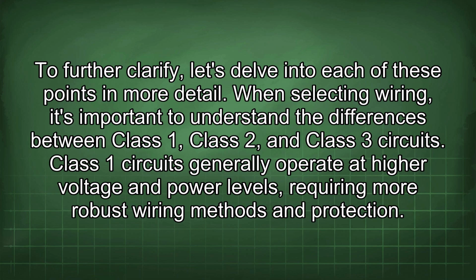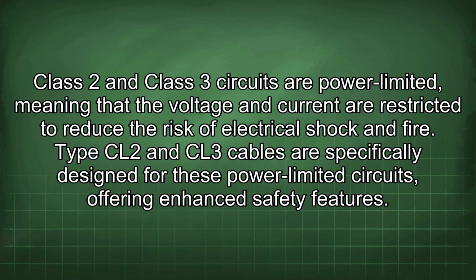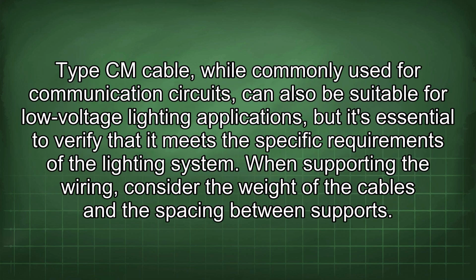When selecting wiring, it's important to understand the differences between Class 1, Class 2, and Class 3 circuits. Class 1 circuits generally operate at higher voltage and power levels, requiring more robust wiring methods and protection. Class 2 and Class 3 circuits are power limited, meaning that the voltage and current are restricted to reduce the risk of electrical shock and fire. Type CL2 and CL3 cables are specifically designed for these power limited circuits, offering enhanced safety features. Type CM cable, while commonly used for communication circuits, can also be suitable for low-voltage lighting applications, but it's essential to verify that it meets the specific requirements of the lighting system.